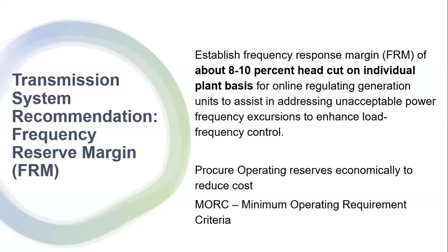So if I lose that generator, say a 250 megawatt unit, and so many bad things happen to the system, I'm going to make sure I procure operating reserves to cover that. And it has to be not just megawatt, it has to be at an appropriate location, such that once I call that unit, it can serve that load.